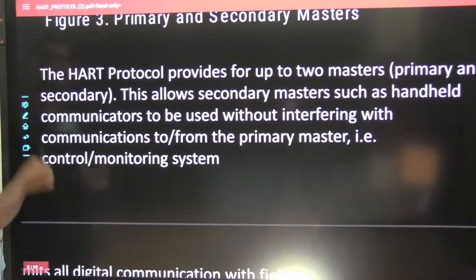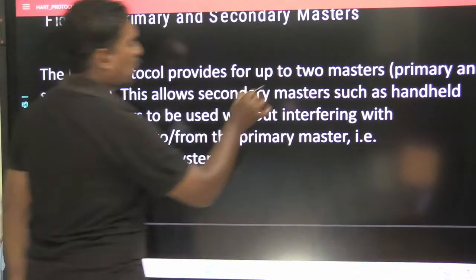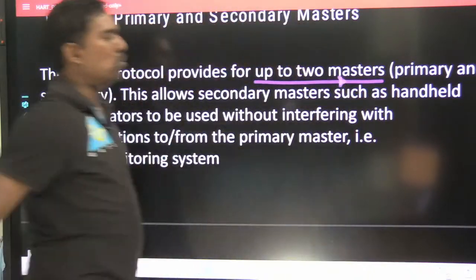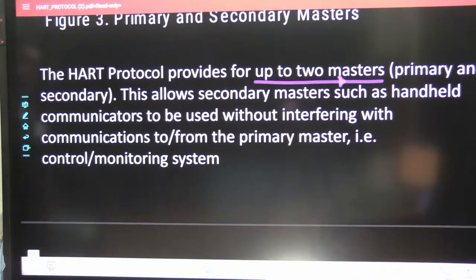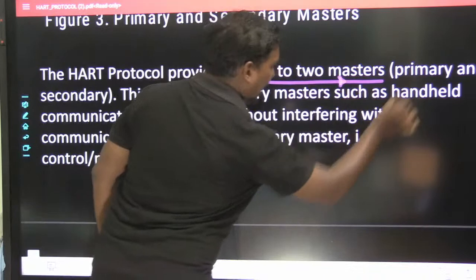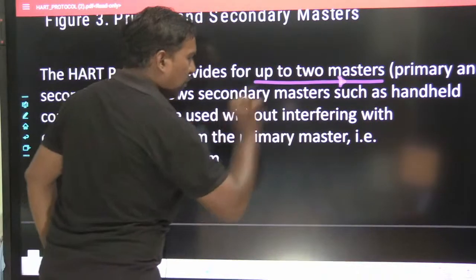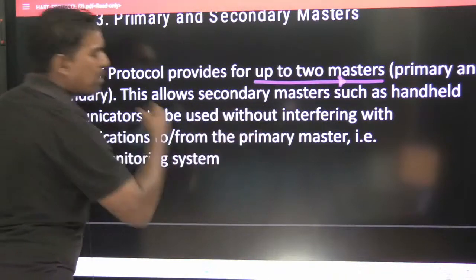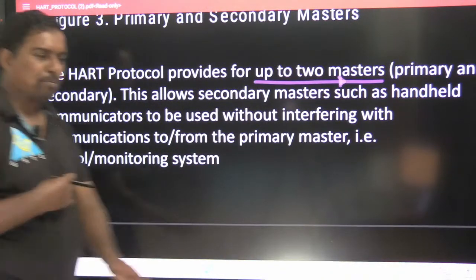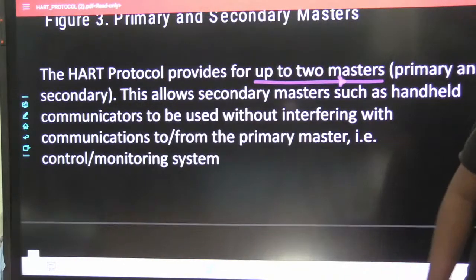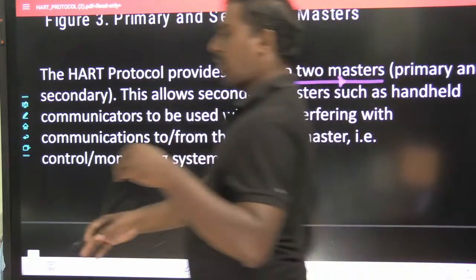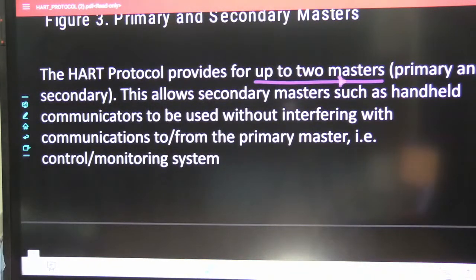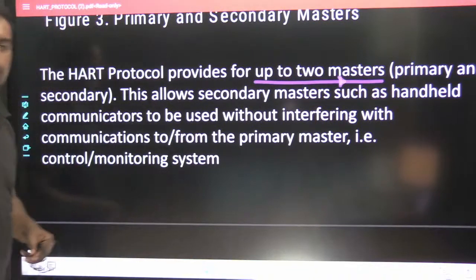See, the HART protocol provides for up to two masters, primary and secondary, maximum two masters. This allows secondary masters such as handheld communicators to be used without interfering with the communications to and from the primary master. Do you understand? Without disturbing the primary master, they are able to communicate.